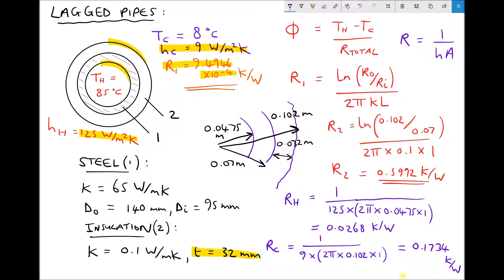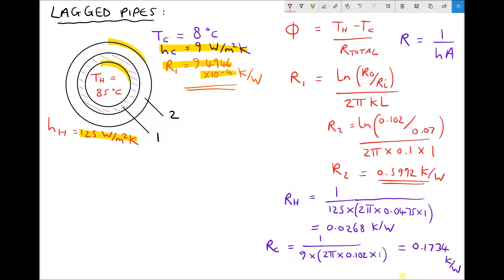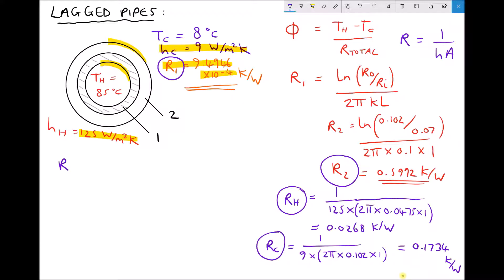Now we can do our final calculations. First, calculating the total thermal resistance — we have four thermal resistances to add together: the thermal resistance of the steel R1, the thermal resistance of the insulation R2, the thermal resistance due to the fluid contact inside the pipe RH, and the thermal resistance due to the fluid contact on the outside of the insulation RC. Adding each of those together, the total comes out to be 0.8003 Kelvin per watt, accurate to 4 decimal places.